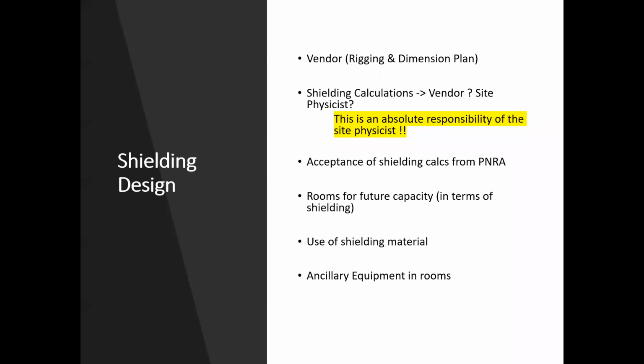The first thing is this shielding design should be based on the vendor specifications, riggings, and the dimension plans. I should not end up with shielding calculations for a bunker where I cannot put my machine afterwards. So all rigging and dimension plans should be obtained from the vendor before starting all these shielding calculations. You can get shielding calculations from vendors, or the site physicist is required to do that.